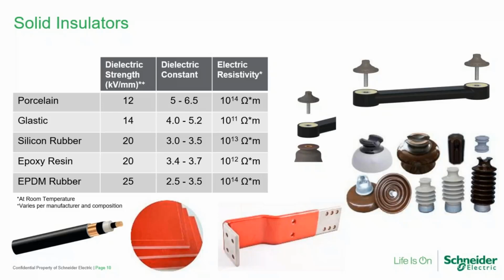And when you think about the type of technology that it takes to do solid insulated switchgear, you're actually talking about very similar technology to what's being used on medium voltage distribution cable. This would be ground shielded medium voltage cable that we've been using for quite a long time. We have been able to take that style of technology and use it inside of the switchgear, letting us shrink down that footprint and get a much longer lasting, more reliable, lower maintenance style of switchgear. So these are the different things that need to be considered when designing solid insulated switchgear. I see you got a couple more questions.